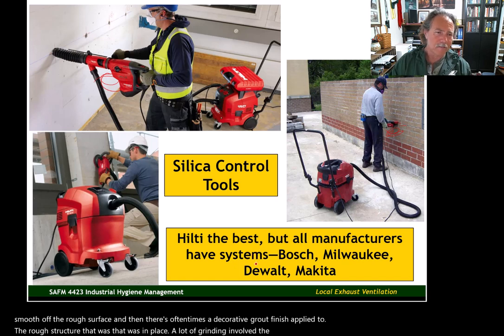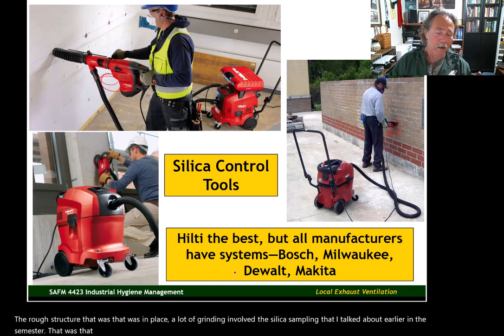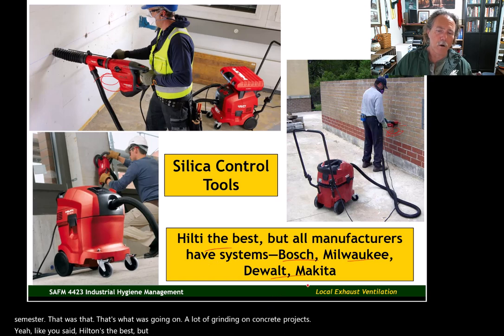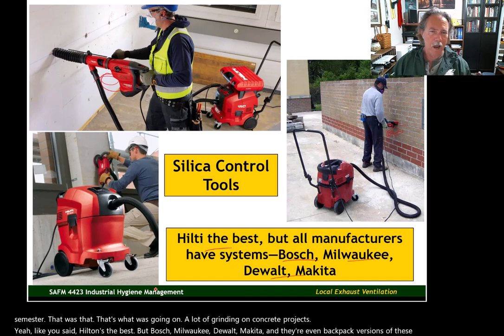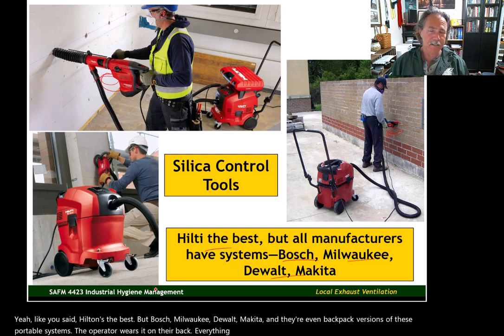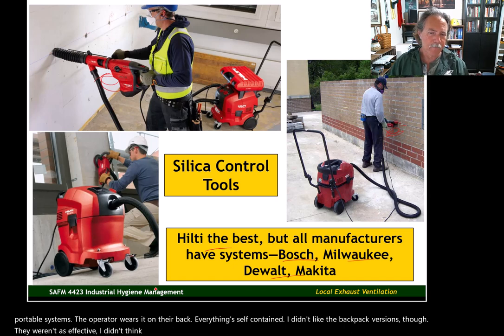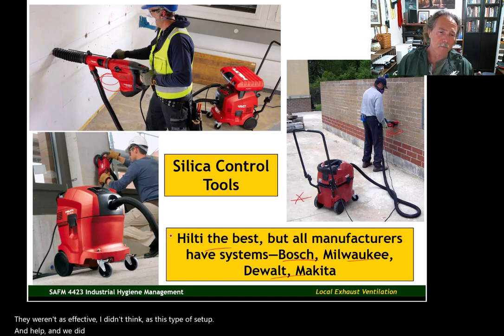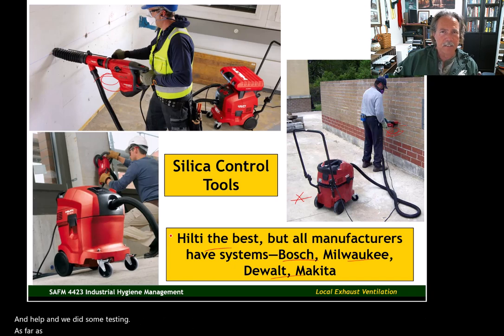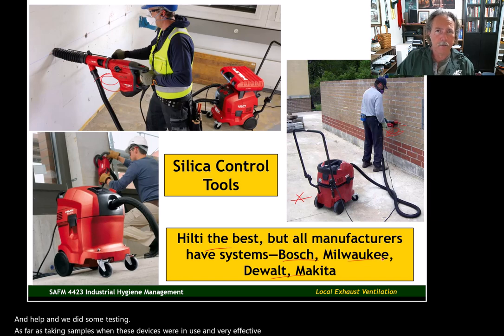The silica sampling that I talked about earlier in the semester, that's what was going on. A lot of grinding on concrete projects. And like I said, Hilti's the best, but Bosch, Milwaukee, DeWalt, Makita, there are even backpack versions of these portable systems. The operator wears it on their back. Everything's self-contained. I didn't like the backpack versions, though. They weren't as effective, I didn't think, as this type of setup. And we did some testing, taking samples when these devices were in use, and very effective removal of the contaminant.